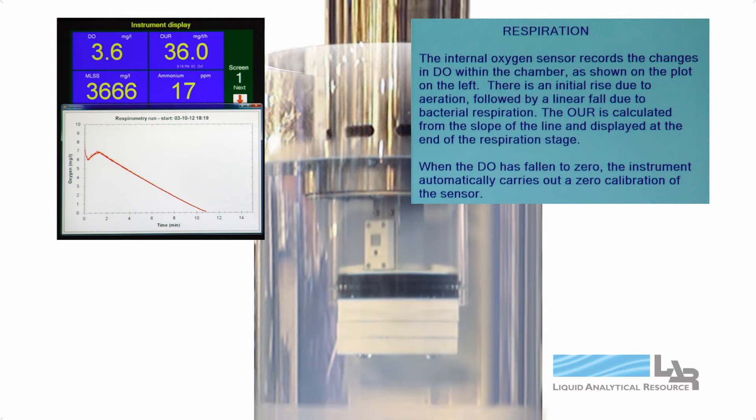An internal oxygen sensor records the changes in dissolved oxygen in the chamber. The plot shows the initial rise in oxygen, followed by a linear drop due to the respiration of bacteria. The oxygen uptake rate is calculated from the slope and displayed at the end of the respiration stage.